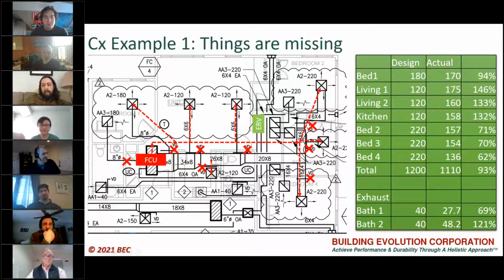What did the testing and balancing report show? Was it just what the fan coil unit was putting out as a total, or was it actually individual readings for each of the elements? So did they show this? They showed, not in green. They didn't have a green box like this, but they had a white table. And it showed like design versus actual, and they all looked like this. Yeah, okay. That's the testing and balancing reports I've seen. They always are like 1 CFM off, as if they balance them exactly perfectly. So, with the volumetric dampers, I don't see how you could balance them.